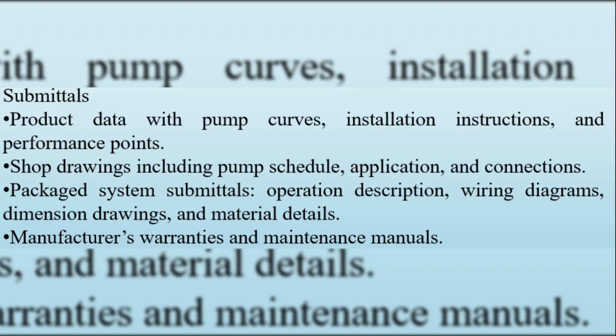When contractors submit their documentation, it needs to cover everything clearly. That includes product data with the latest pump curves, so we can see the exact operating points at the design conditions. They also need to provide shop drawings with pump schedules, layouts, dimensions, and connection details. On the electrical side, we expect wiring diagrams that show both the power wiring handled by the electrical contractor and the controls wiring handled by the controls contractor. For packaged systems, the submittal should include arrangement drawings, a clear description of how the system operates, and details on how it will integrate with BACnet.